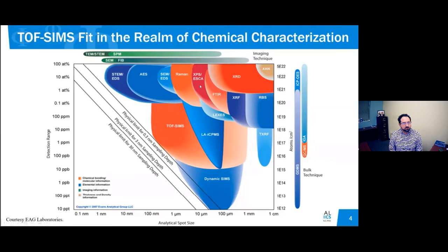This animation will just show how the instrument works. It takes a pulsed primary ion beam and rasters the sample to generate secondary ions. They're extracted and then travel through a mass spectrometer, where they're separated by their mass to charge. Lighter ions will hit the detector first, and heavier ions will hit later, as you can see in the mass spectrum.